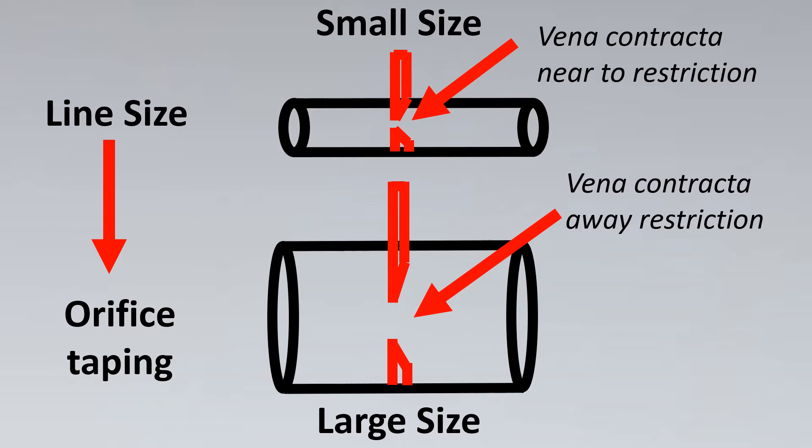The line size basically helps us to decide which orifice tapping to take. If it's nearer to the restriction, the Vena contracta, the tappings would also be taken from near to the orifice. And away is the Vena contracta from the restriction, the tappings are taken from that distance or as much approximation as possible from that distance to get the best DP that is available.